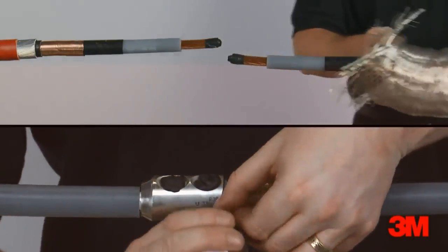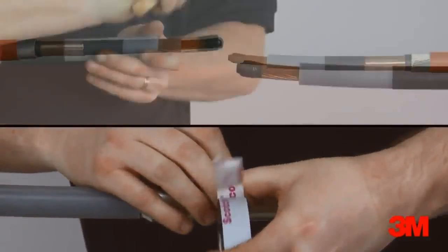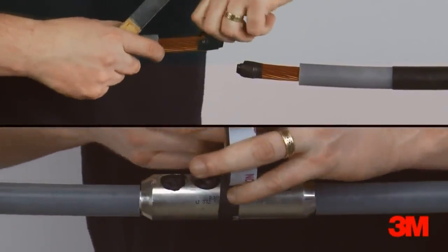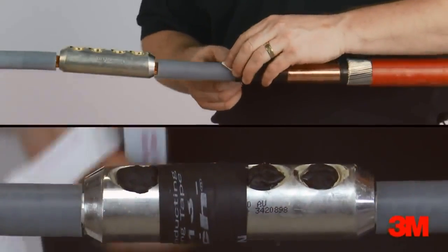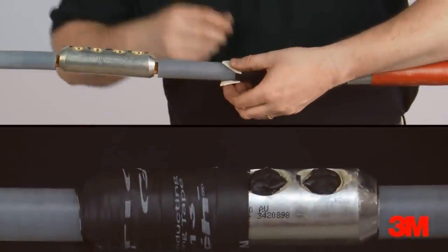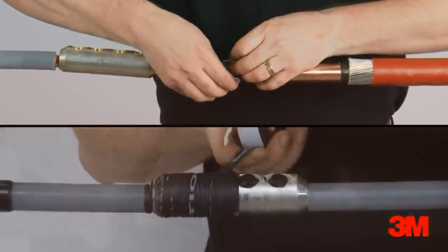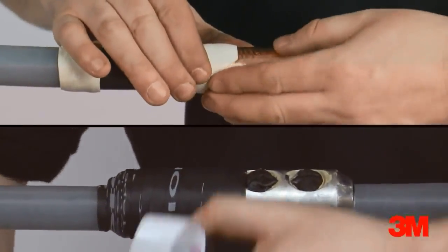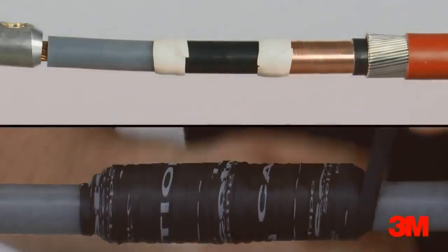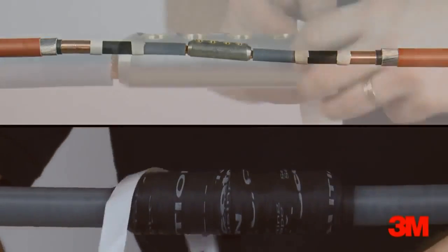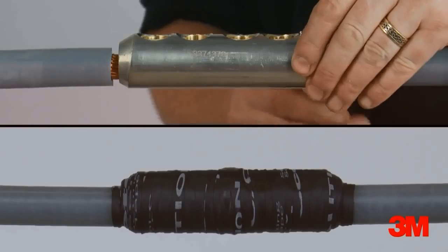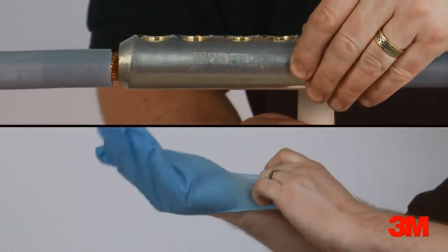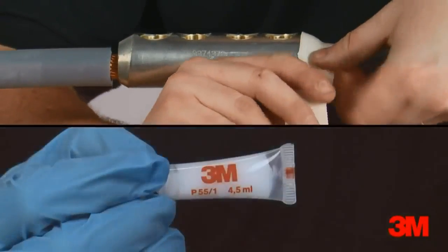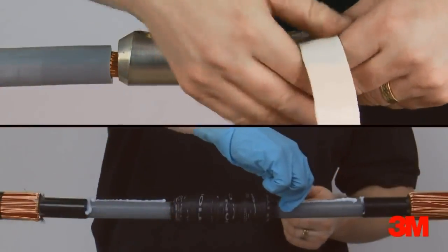Scotch 13 semiconducting tape is used to overtape the connector. Layers are applied tightly around the connector, overlapping the primary insulation on each side. This stage replaces the need for a heat shrink tube used in competitive heat applied alternatives. 3M invented cold shrink technology over 30 years ago. Our cold applied products utilize the unique cold shrink delivery system, designed to make cable jointing, insulating, termination and abandonment as simple as possible.